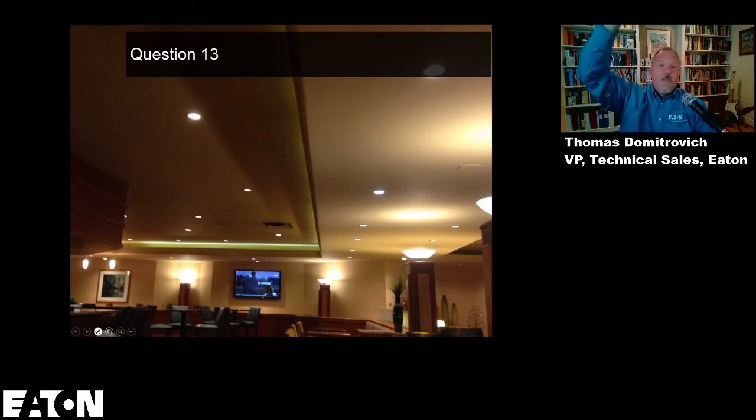I could reach in and pull it out and then replace the whole strip, because some of that's like a string light and you just plug them in. I don't need much access. As long as I can reach my hand in there and pull it out, I'm good. But I do have to be able to replace any of the LED drivers, and I have to have clear access to all of that.